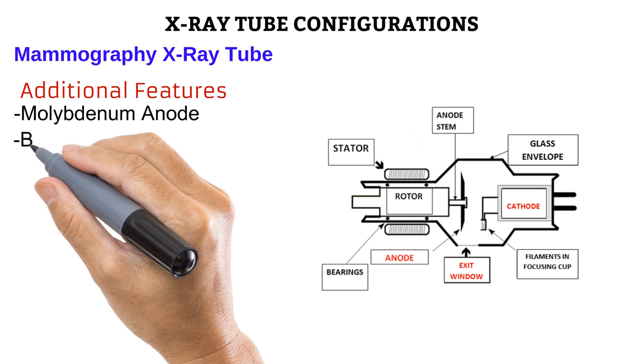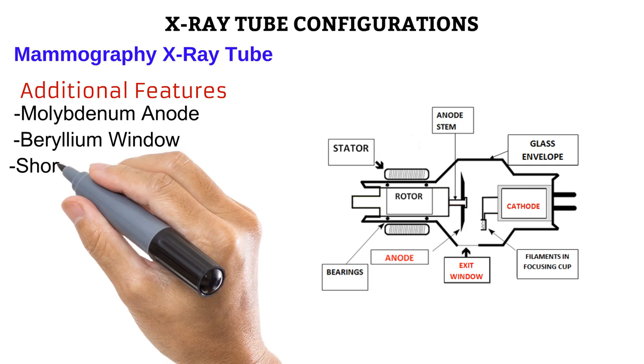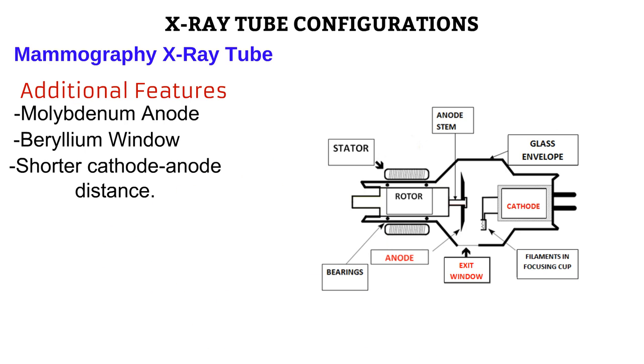Also, their exit window is made of beryllium instead of the glass in standard X-ray tubes. Like we mentioned, the photons produced by mammography tubes have a lower KV or energy. If the exit window was made of glass, it would absorb these low-energy photons. By using a much thinner material like beryllium, photons can easily pass through. Also there is a much shorter distance between the cathode and the anode. This allows less work to be done in moving electrons from the cathode to the anode. When less work is done, there is less heating and the life of the filament is prolonged.